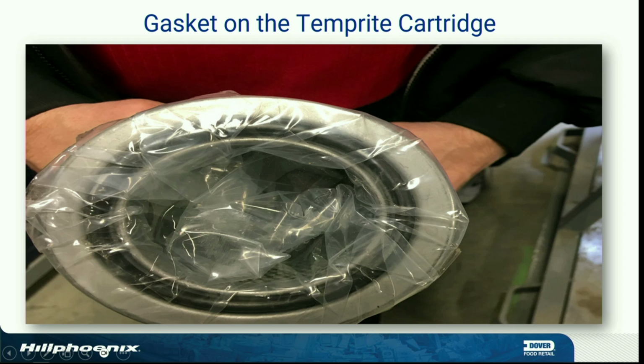The new filter will have an O-ring, and almost every time you take these apart, what's that O-ring look like when you pull it apart? Gone. It's either gone or it's expanded out, right? Because it's filled up with CO2 and oil and has expanded, okay? So that's a good indicator. If you go up to a service call every few months, I would do a differential pressure check across those separators, whether it's Temprite or if it's Westermeyer. If you see 0 or greater than 12, I would recommend changing those filters, guys. It only takes 25 PSI differential to blow that filter apart that we saw earlier. 25, it's not a big deal.